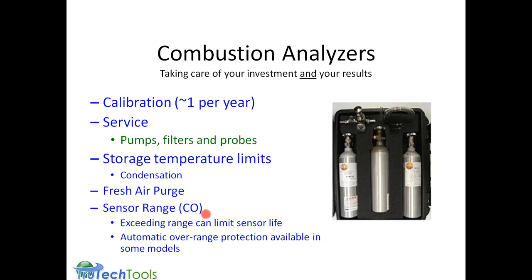The sensor range for carbon monoxide is something where you don't want to go into the overrange condition. I believe it's 4,000 ppm for the 327. You can effectively go about double that for very brief periods of time, but you don't want to go there. There is an automatic overrange protection. I believe in the 327 it's set to about 3,700 ppm, where it's automatically going to shut off to stop it from bringing in more and higher levels of gas. But when it shuts off, the gas is trapped inside. So you want to get it back into fresh air and purge again on fresh air.